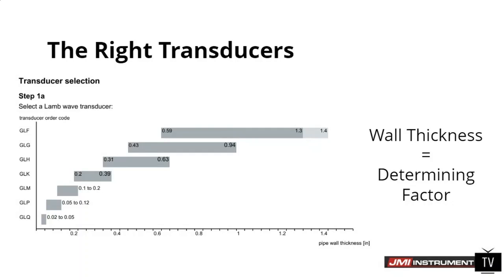Sound likes to travel through dense mediums like water and metal. It doesn't really like to travel through gases. So with gases, we have to do some things to ensure that we can get a signal through that light density medium. You can see here the wall thicknesses for the different frequency of transducers. So this is basically the determining factor. The outside diameter of the pipe is also a factor, but for the most part, we look at the wall thickness more than anything.